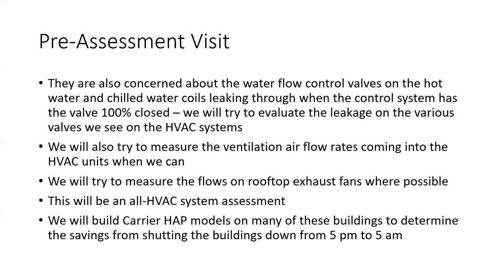through, and it could be that they're cooling down the air and heating it up and cooling it down and heating it up. And also it could be that the chill water valves are leaking through. So we've got a bunch of additional thermocouple readouts, and we're going to try to evaluate some of this.